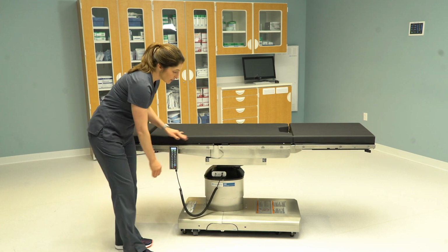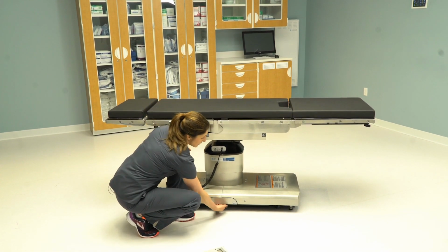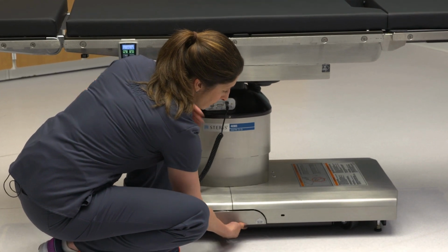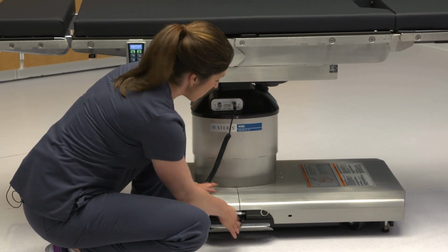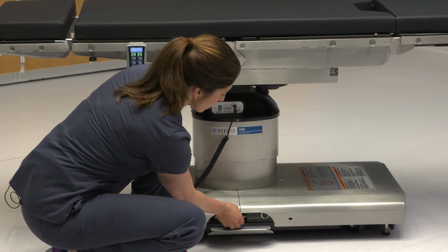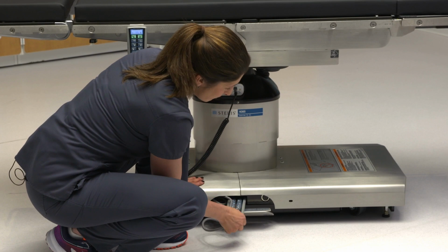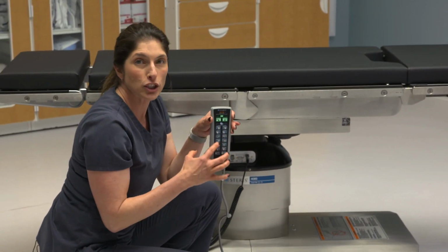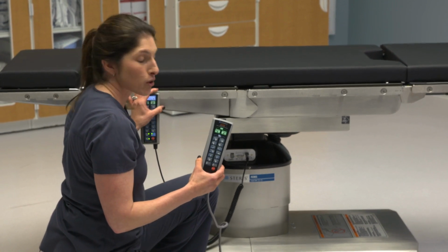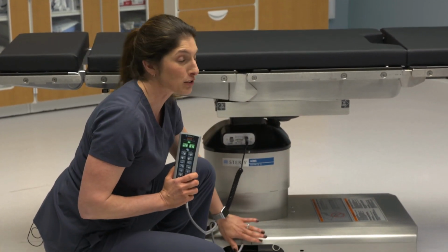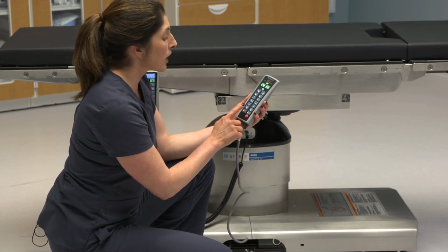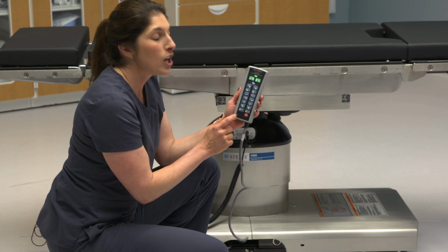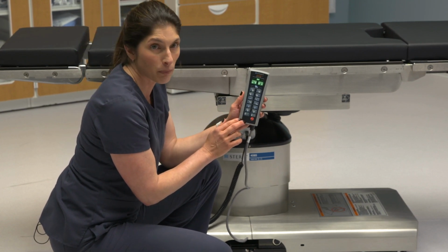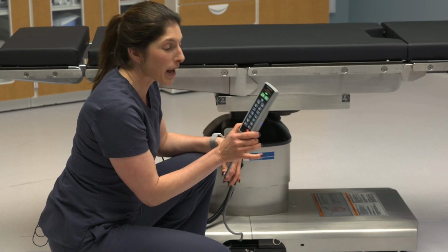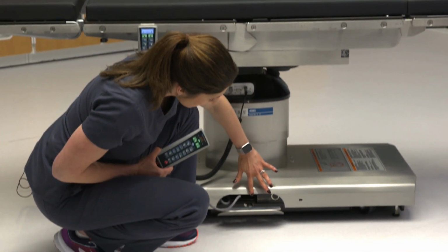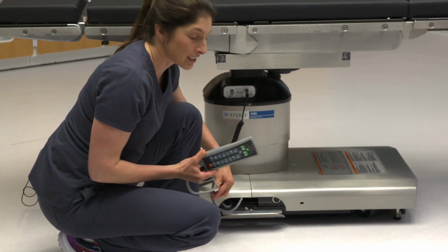On the 4085, you have a drawer down here on the patient right at the base. You can put your fingers right under here and pull down, and this foot pump will come down, and there's a backup hand control tucked in this little drawer right here. So you can pull that out, and you've got full articulation capability on this hand control, just like you do on your main hand control. Important to note that this hand control is already plugged in down here, so there's nowhere to plug that in. It's already plugged in for you. And you've got all articulations to include lock and unlock. The only thing you don't have access to is return to level. And a little trick to putting this back is that you want the hand control to go on the right-hand side of this little drawer and the cables to go on the left-hand side of the drawer.